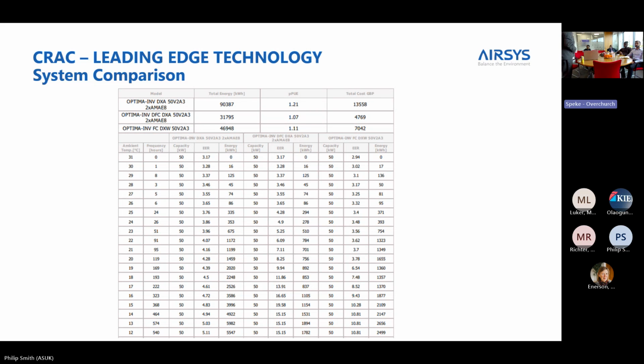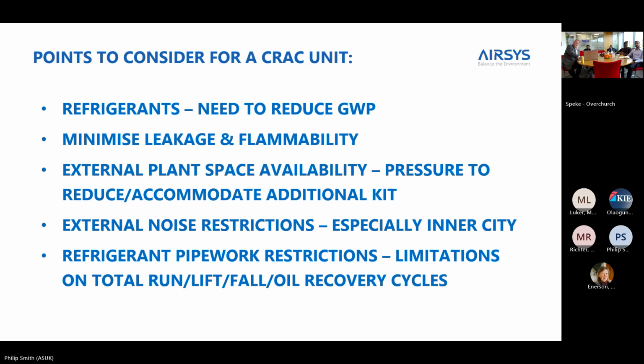So if you can get away with using fresh air within a CRAC unit, you're reducing the energy input by 67%. So from an energy principle alone, it has a positive payback of a year, 18 months, something like that. There are points to consider. You may all well be aware of all of these.